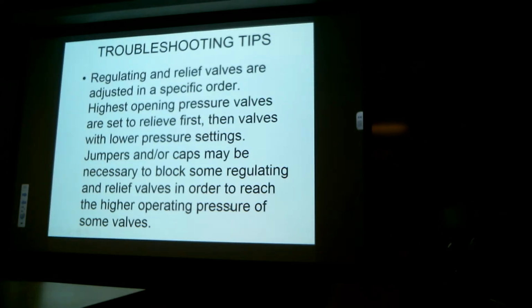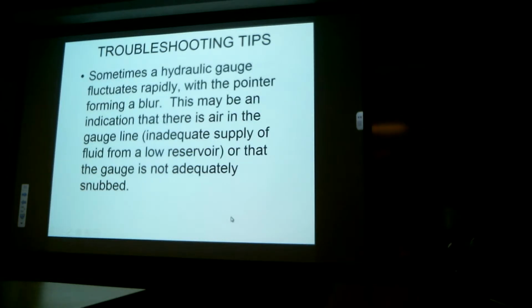Once that's been adjusted, then you can adjust, usually, the system relief valve. But again, you're going to have to sometimes jumper or block the actuation or the operation of the unloading valve. Why you do that? And this isn't as difficult as you might think. You don't have to use an engine-driven pump in order to get the flow. You can use a hand pump in order to be able to adjust pressure. You just have to block the other components that are in the circuit that might control it before the particular device you're trying to set is reached. Okay. Anything else? I think that's about it.